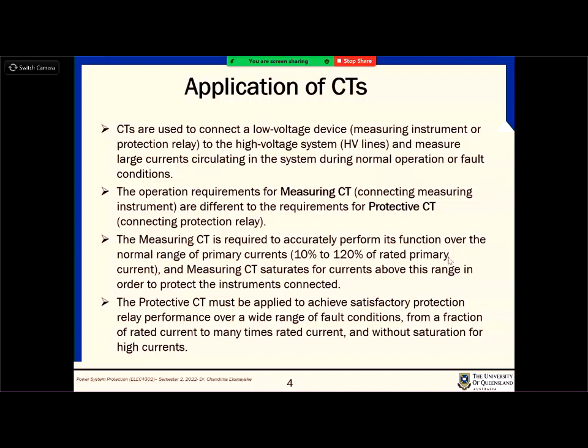Otherwise, what happens? Let's say your secondary circuit can measure up to 10 amps, and 10 amps corresponds to your full loading conditions. During a fault, that can go up to 100 amps. If you try to measure 100 amps in your secondary circuit in a measuring device, what happens? That will basically collapse. It depends on the situation, it will do erroneous measurements or be completely destroyed, right, because of the high current magnitudes.